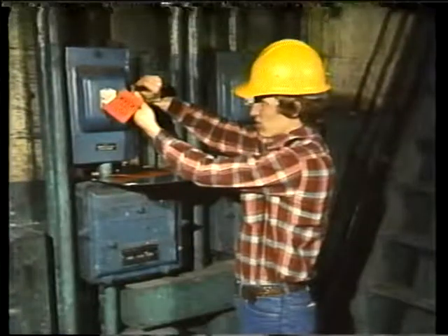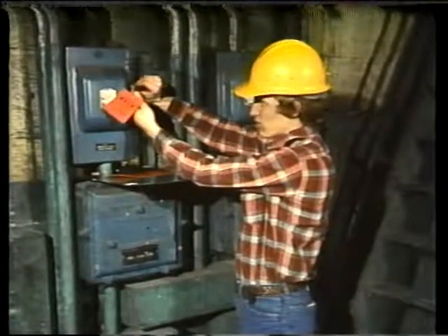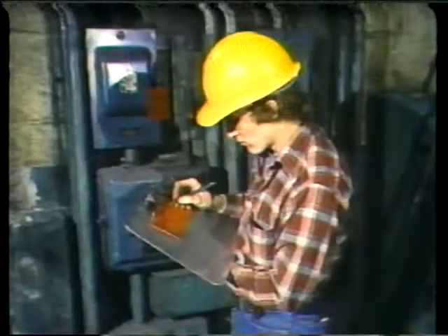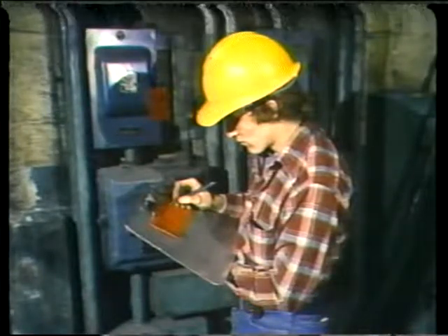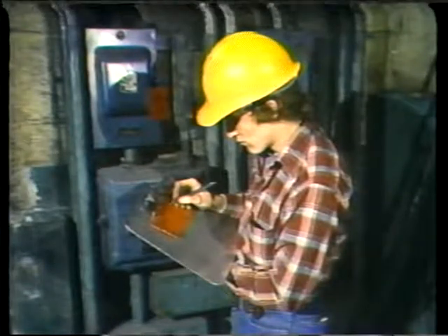When a complete list of what has to be tagged out has been drawn up, it has to be approved by an operations supervisor. This is one more check to ensure that it's right and it keeps operators informed of the status of their equipment. When the tag out has been approved, the tags will have to be hung and checked off one at a time. Now, this step will probably be done by the operators in charge of the equipment being tagged.